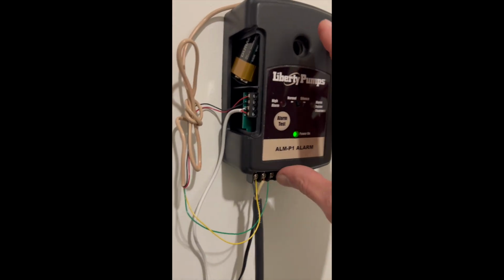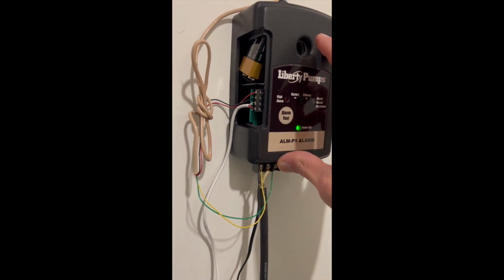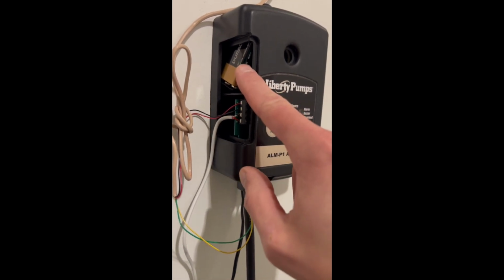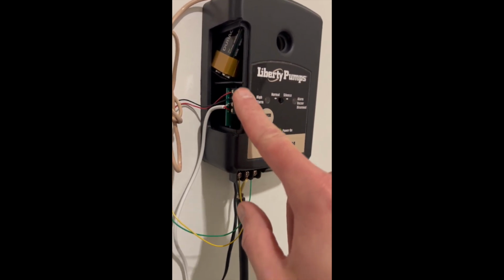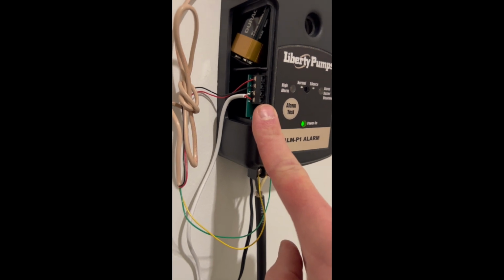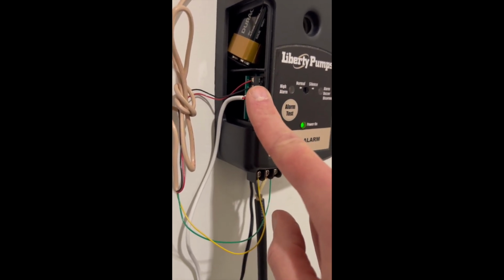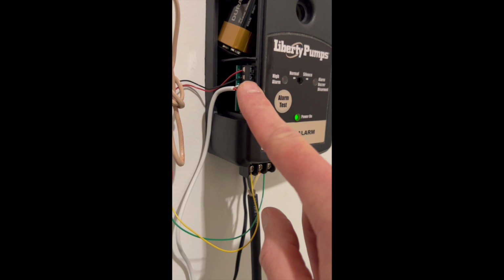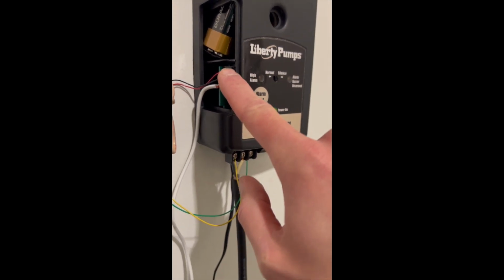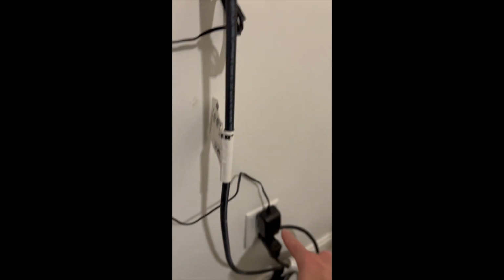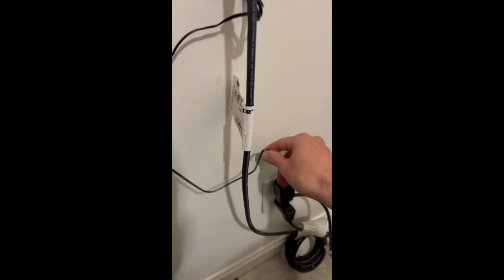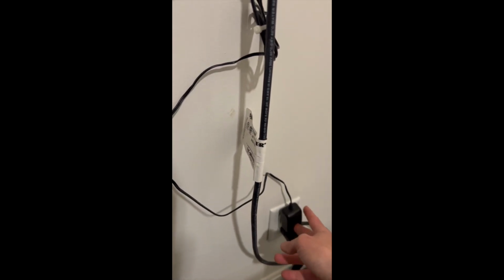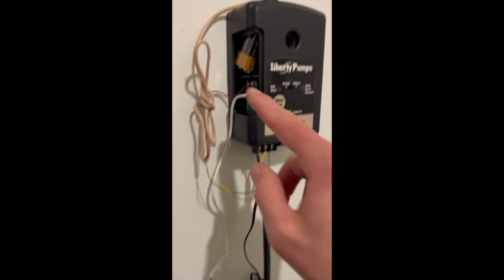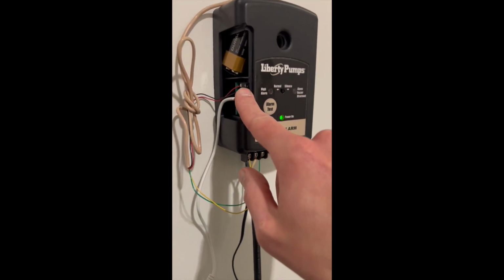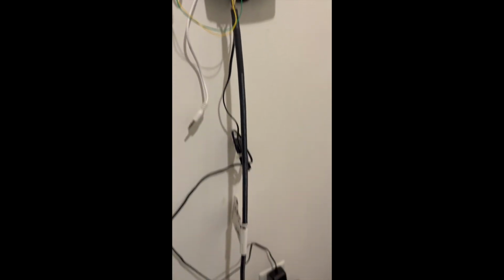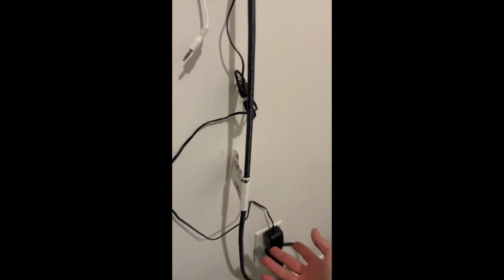But one of the nice features this particular model has is it has not only the battery backup, but it has these connectors on the side. These top two are an auxiliary power source. So I have a plus and a minus. These outlets here are directly tied to the output of this transformer. This is 11 volts that supplies this unit. So on these contacts, I get 11 volts whenever this outlet is working properly.